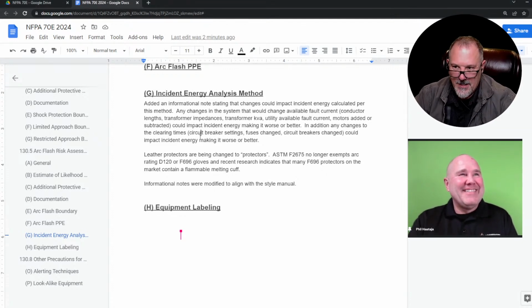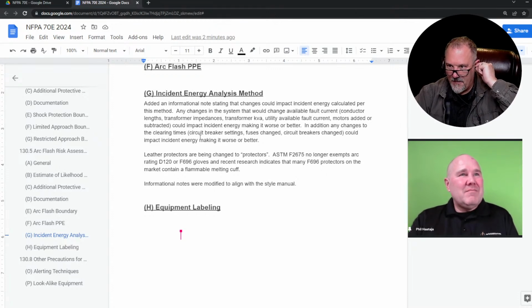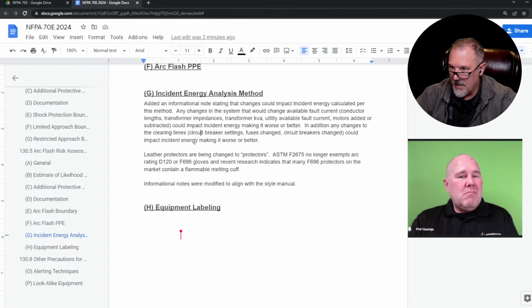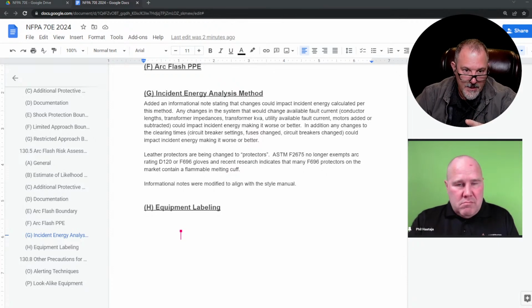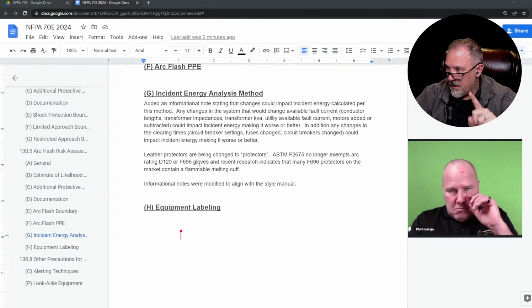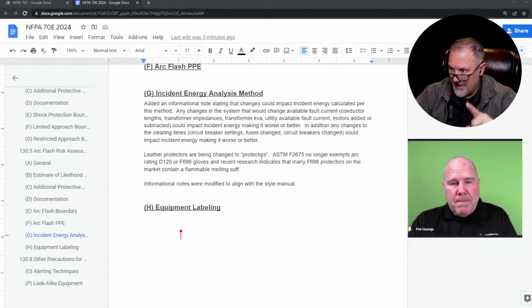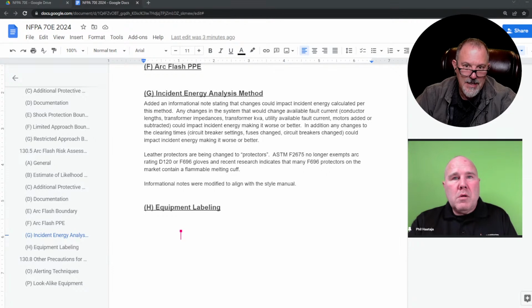All right. So gauntlet is above the cuff. Gauntlet is above the cuff. That's what Robert is saying. So leather protectors. Let me go back to this now. Where they removed leather protectors, the reason was no longer exempts arc rating for gloves, and recent research indicates that many F696 protectors on the market contain a flammable melting cuff.